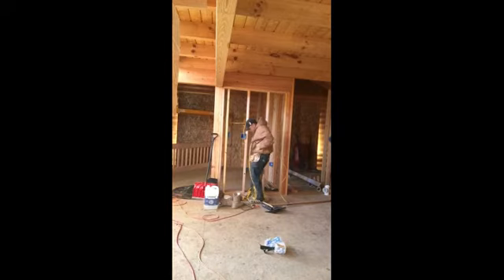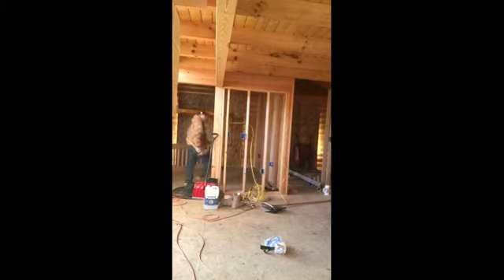for the boxes for switches, which will be about 48 inches on center from the OSB subfloor. Be sure to take into account double, triple, and even quadruple boxes when needed. Remember, students, that if you have 2 switches on the wall, it's going to have a double box. Sometimes you have a GFI with two separate plugs on the side, like in the kitchen where I have it. That's going to be a three configuration box, and then you may even have four switches in a box. You know, if you're out near the vestibule or something, and you got light switches outside and inside that have to be flipped. So be mindful of all of that when you start nailing in boxes.